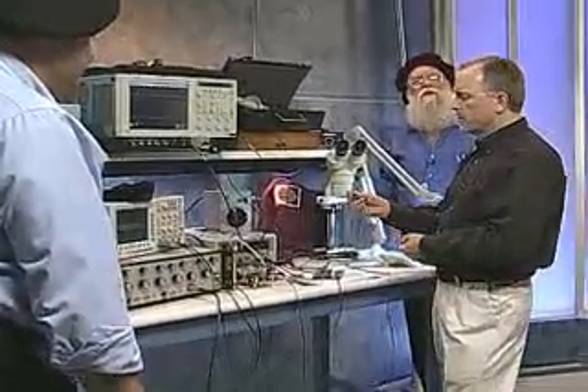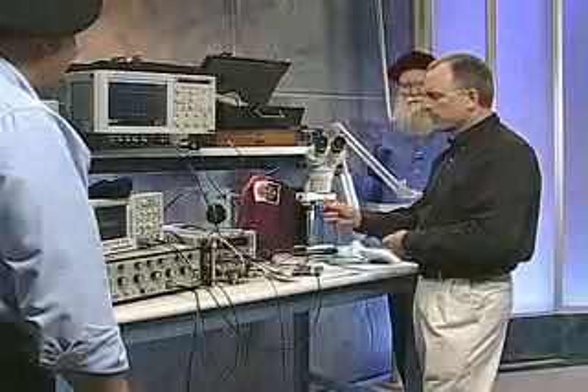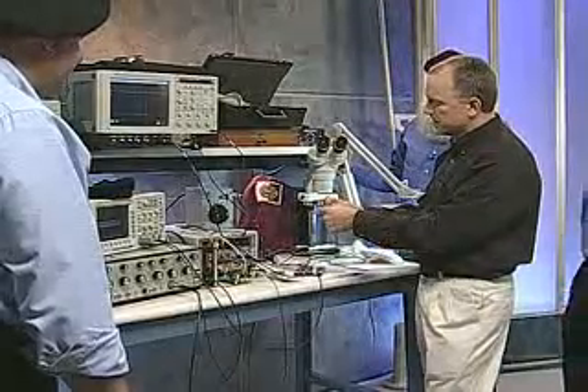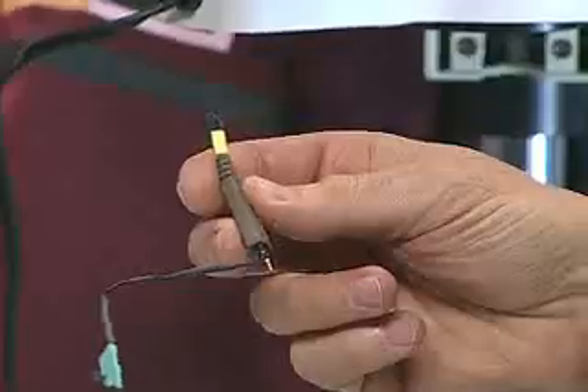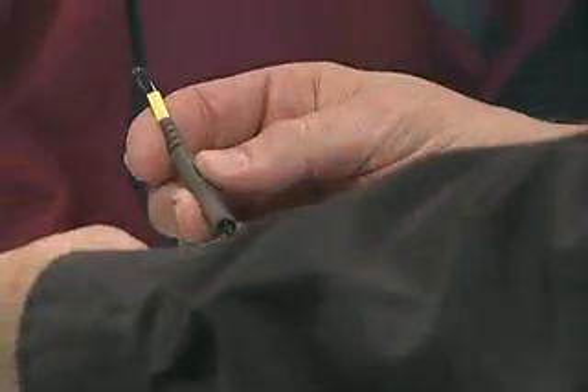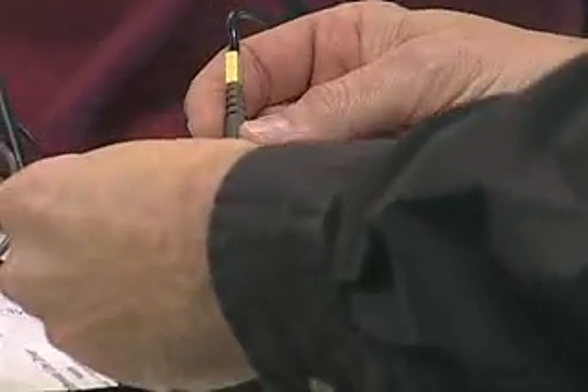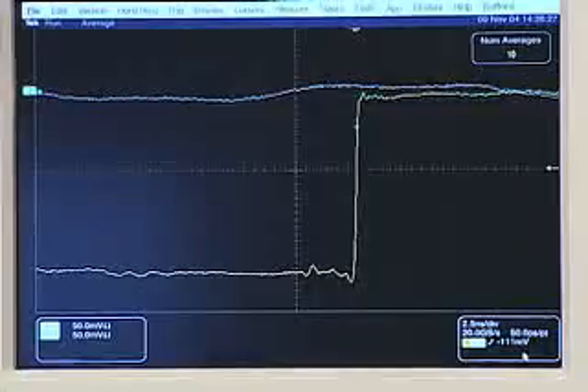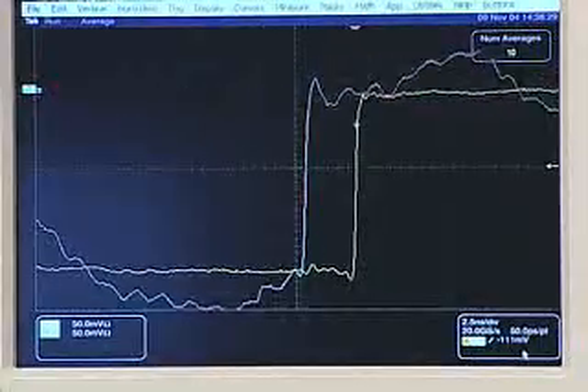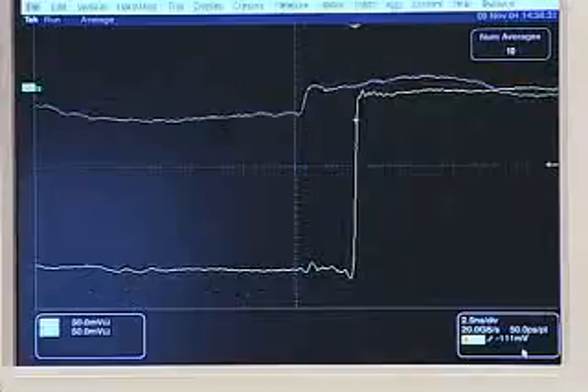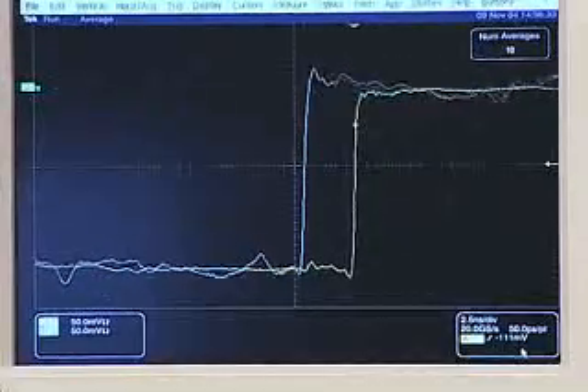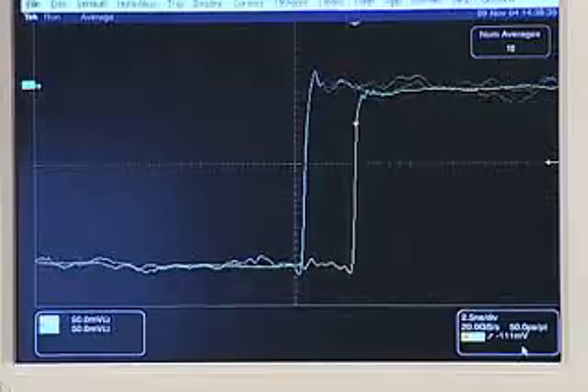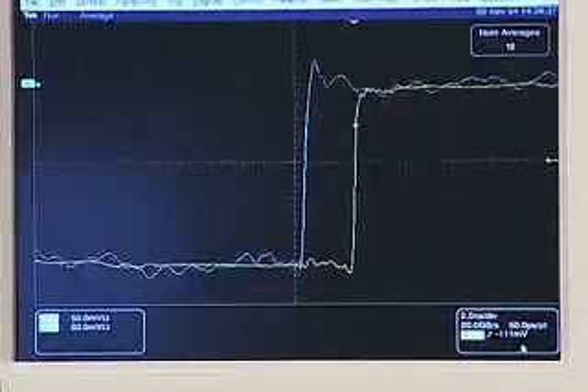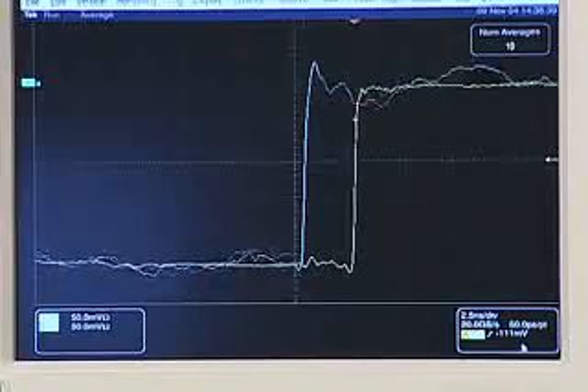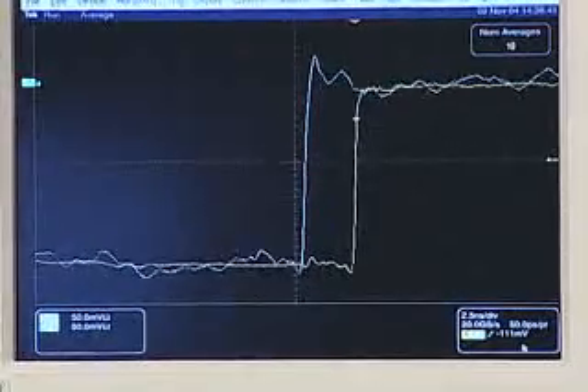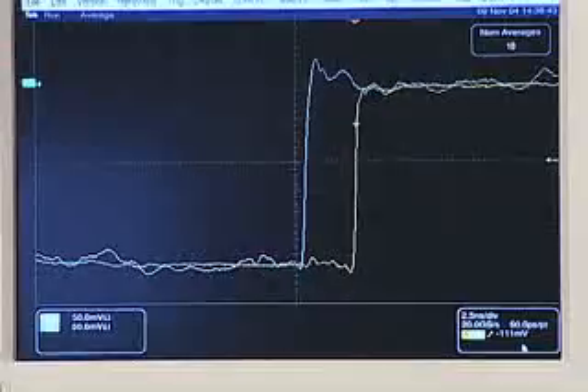So let's take that longer ground lead that Bob was talking about before. And this one's not even 6 inches. It's just maybe a 3-inch lead right here. And let's try to probe. This is about a 200 picosecond step. And we'll try probing it with that ground lead hanging out there. Oh, God, it's a mess. Look at this. It's all over the place. Not only does it introduce that ringing that you were talking about, but look at all the noise it picks up from the other circuits and the other devices on the bench here.